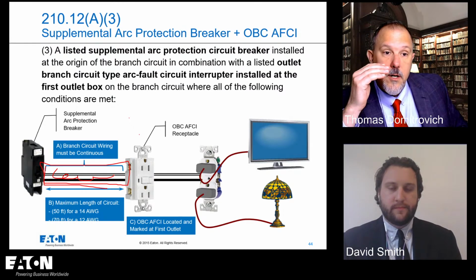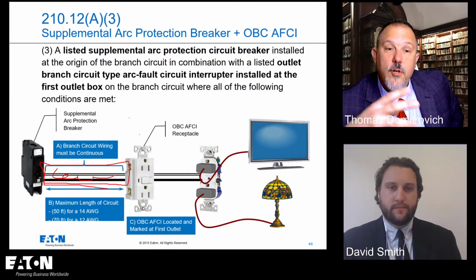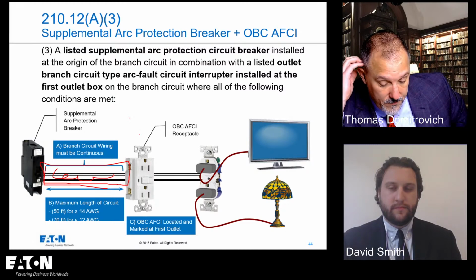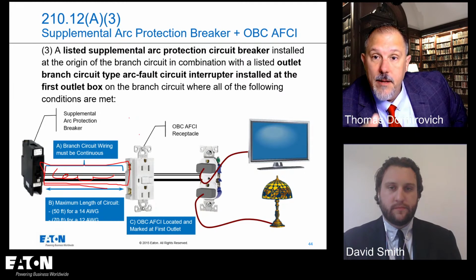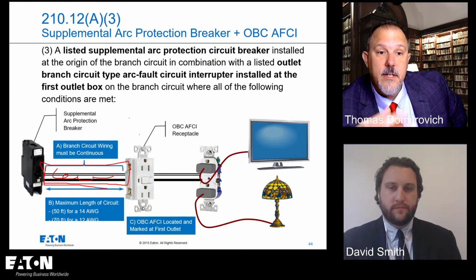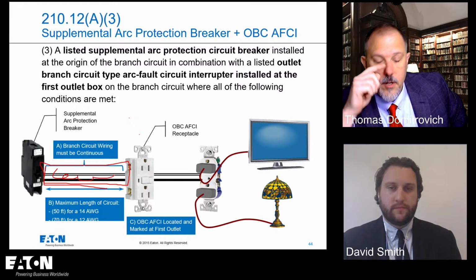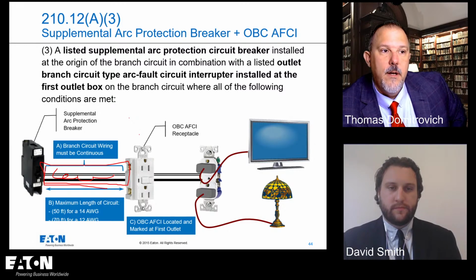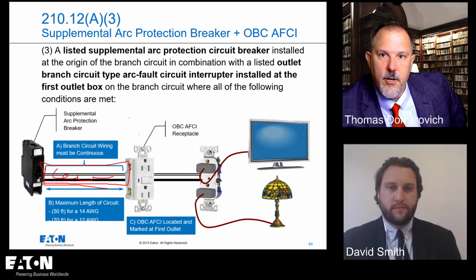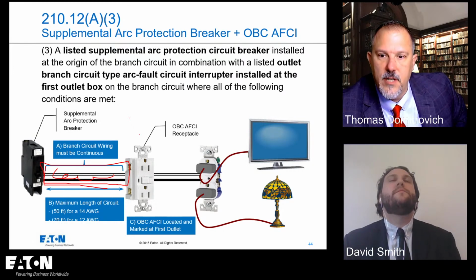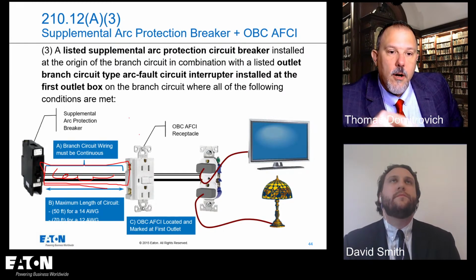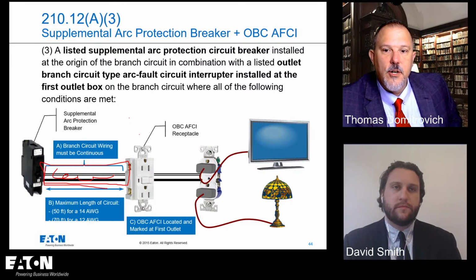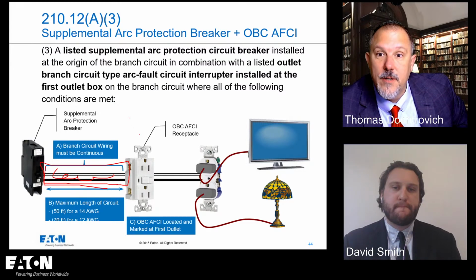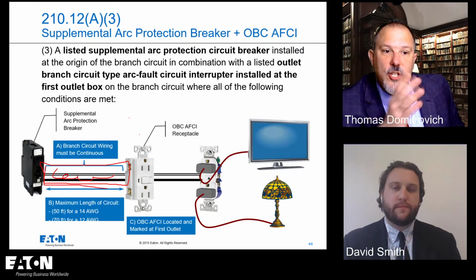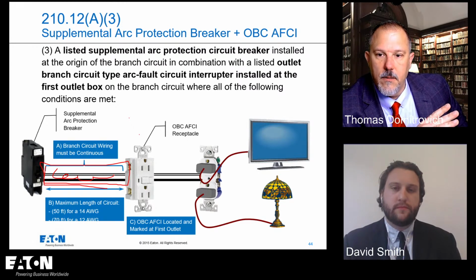Now, arcing faults. You could make an argument. You could say, look, parallel arcing faults and series arcing faults. If you have 100,000 amps available fault current and your breaker could interrupt 100,000 amps, if you have an arc in that conductor, it's going to be more than 75 amps. It's going to be more than 100 amps. It's going to trip the thermomagnetic circuit breaker.